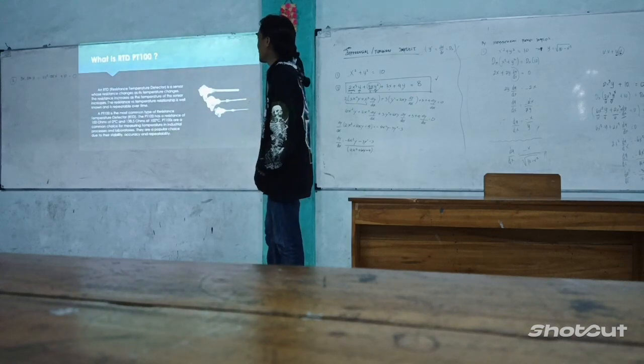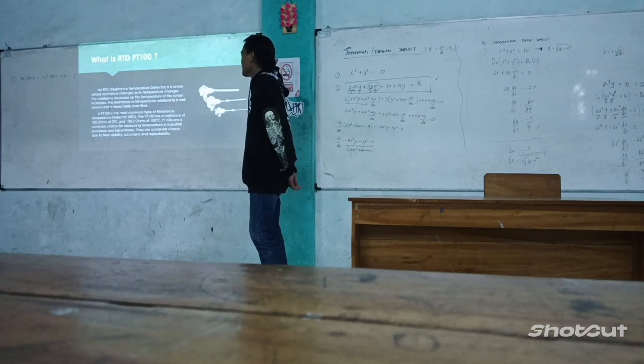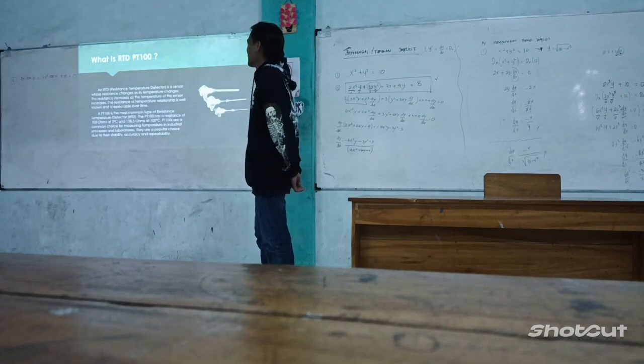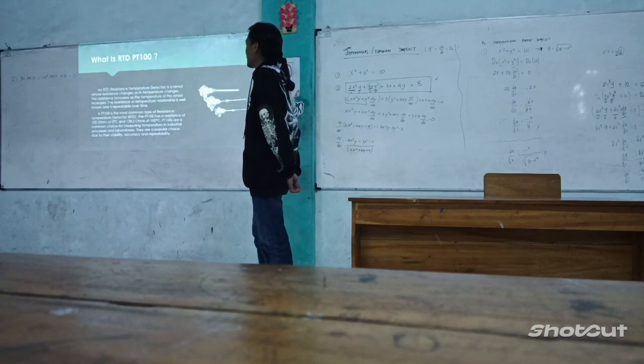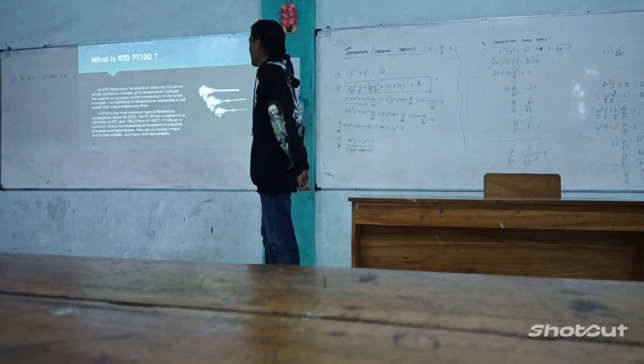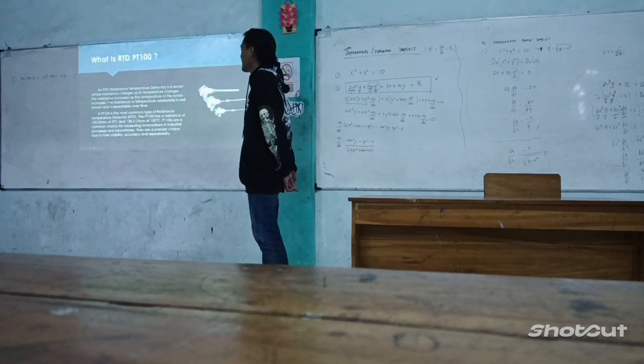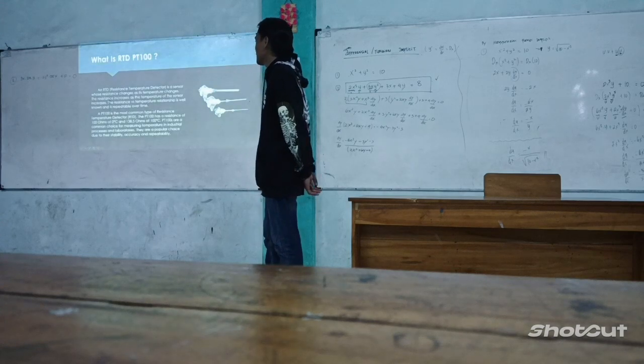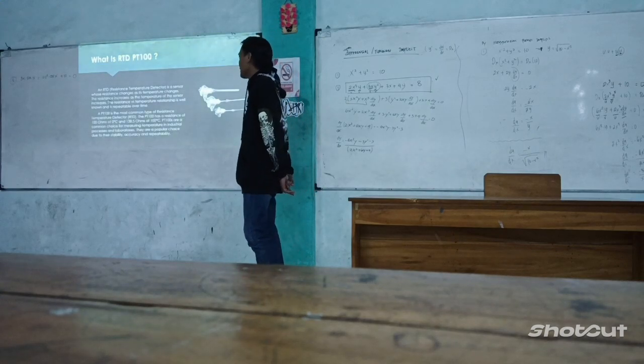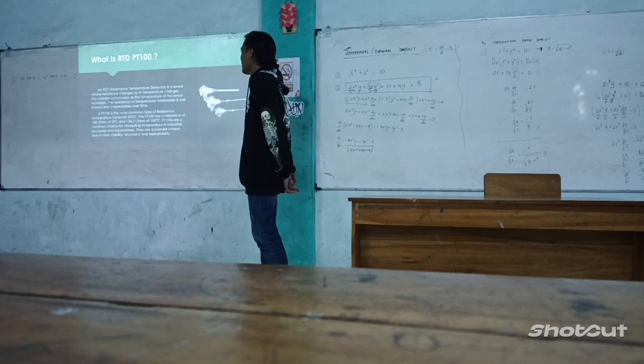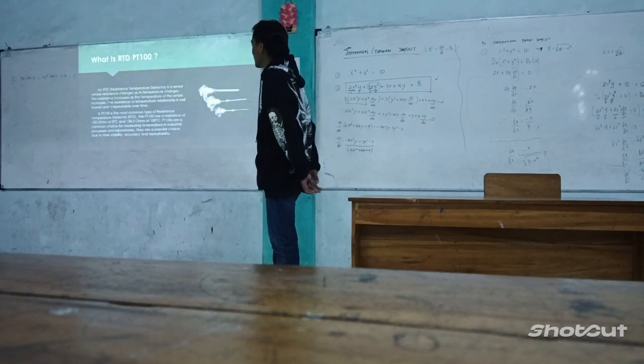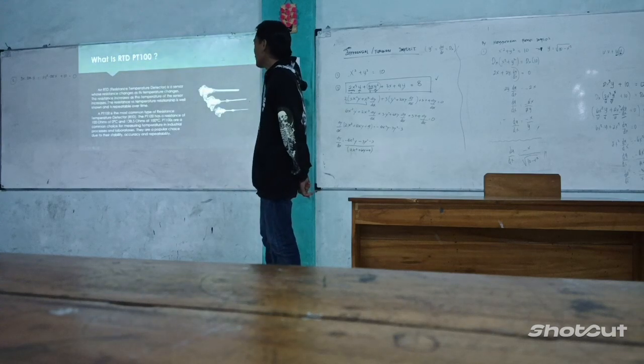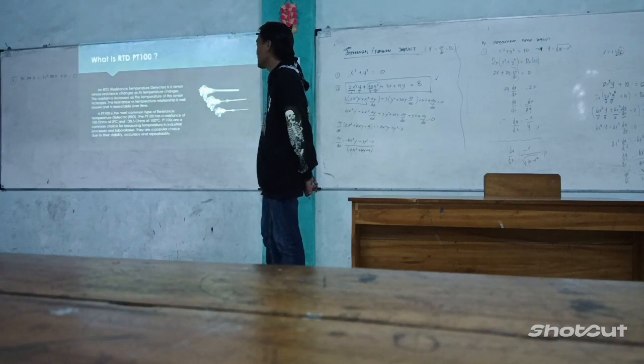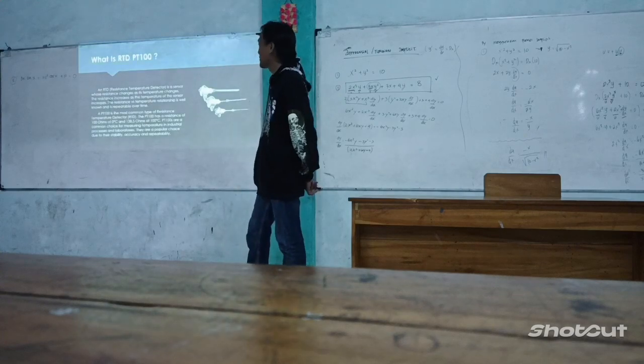An RTD is a resistance temperature detector. It's a sensor whose resistance changes as its temperature changes. The resistance increases as the temperature of the sensor increases. The resistance versus temperature relationship is well known and is repeatable over time. A PT100 is the most common type of resistance temperature detector. The PT100 has a resistance of 100 ohms at 0 degrees Celsius and 138.5 ohms at 100 degrees Celsius. PT100s are the most common choice for measuring temperature in industrial processes and laboratories. They are a popular choice due to their stability, accuracy, and repeatability.